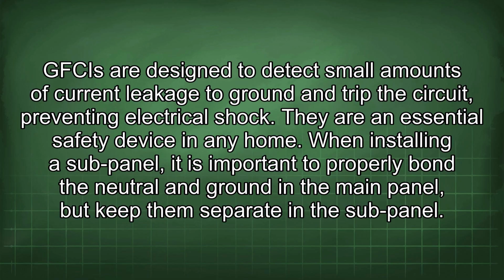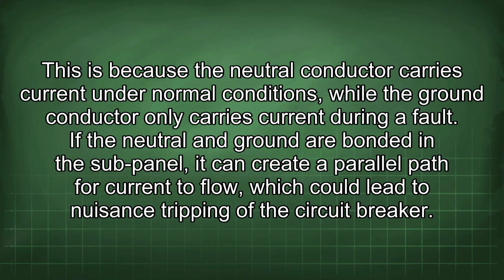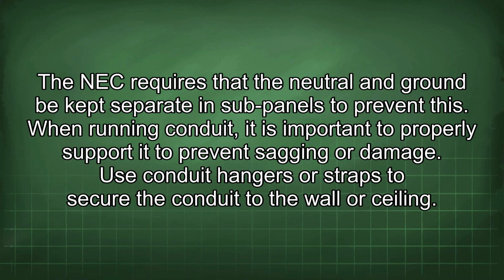When installing a sub-panel, it is important to properly bond the neutral and ground in the main panel, but keep them separate in the sub-panel. This is because the neutral conductor carries current under normal conditions, while the ground conductor only carries current during a fault. If the neutral and ground are bonded in the sub-panel, it can create a parallel path for current to flow, which could lead to nuisance tripping of the circuit breaker. The NEC requires that the neutral and ground be kept separate in sub-panels to prevent this.